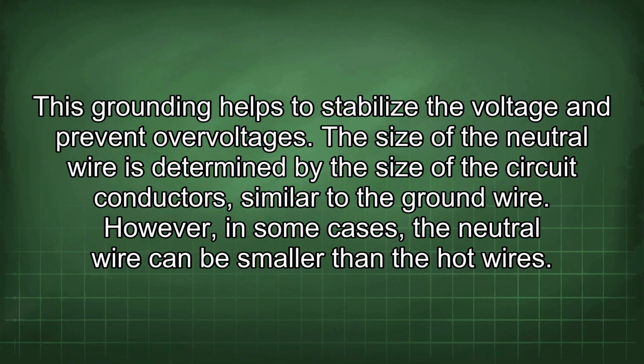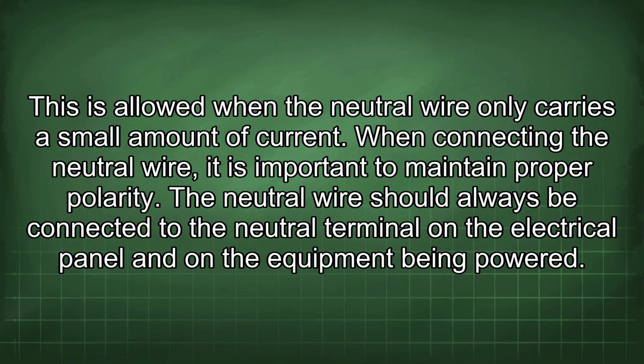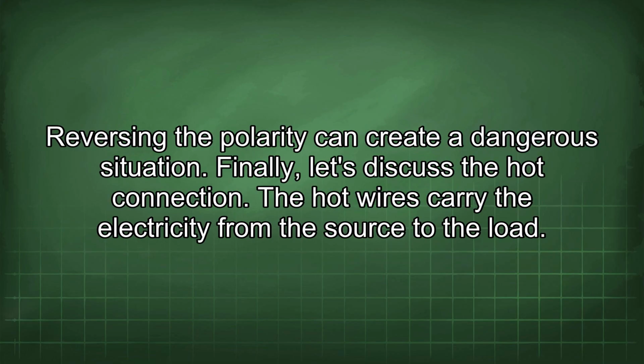The size of the neutral wire is determined by the size of the circuit conductors, similar to the ground wire. However, in some cases, the neutral wire can be smaller than the hot wires. This is allowed when the neutral wire only carries a small amount of current. When connecting the neutral wire, it is important to maintain proper polarity. The neutral wire should always be connected to the neutral terminal on the electrical panel and on the equipment being powered. Reversing the polarity can create a dangerous situation.